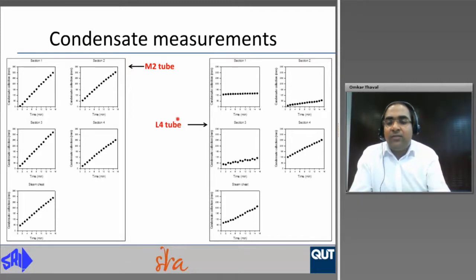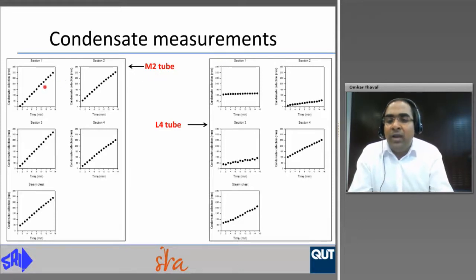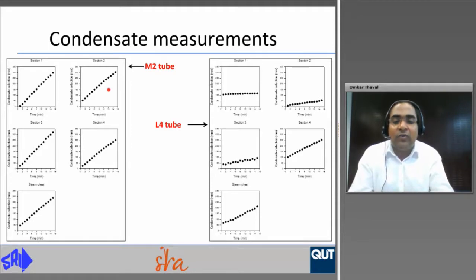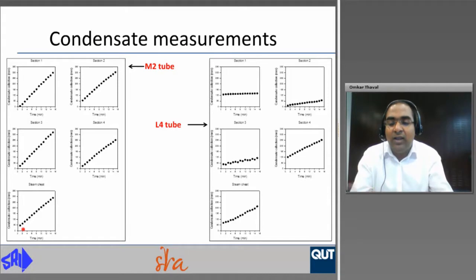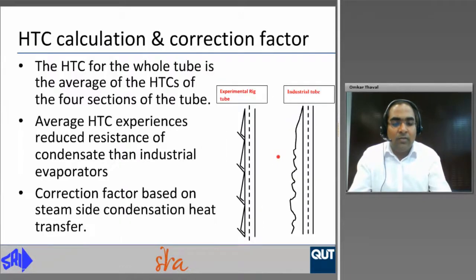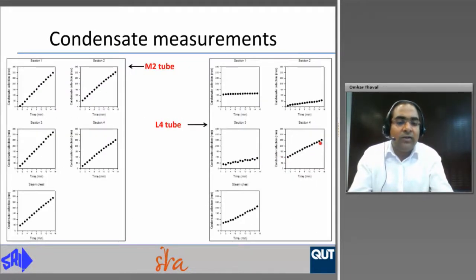The condensate measurements for a medium diameter 2 meter tube show that steady state condensate collection is achieved for all four sections with the M2 tube, confirming that boiling was good and the entire tube was wetted. Some condensate collection on the inner sides of the steam chest occurs due to heat losses. For a large diameter 4 meter tube, juice was boiling only at the bottommost section of the tube and not much heat transfer was achieved at the top three sections.